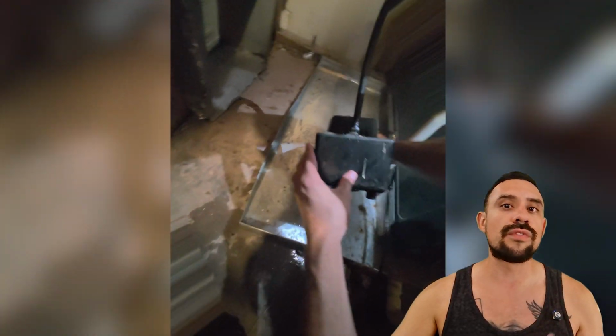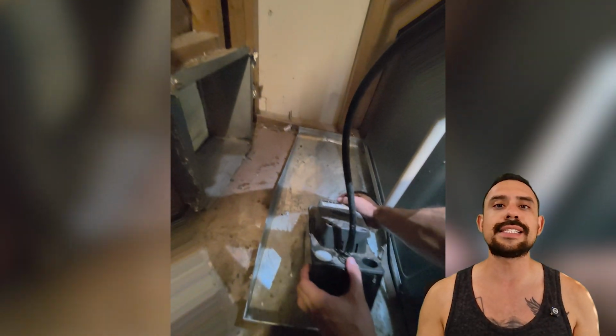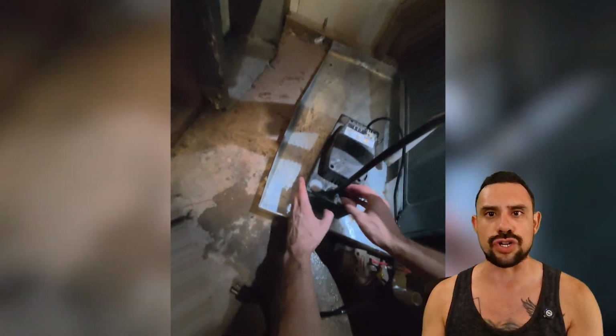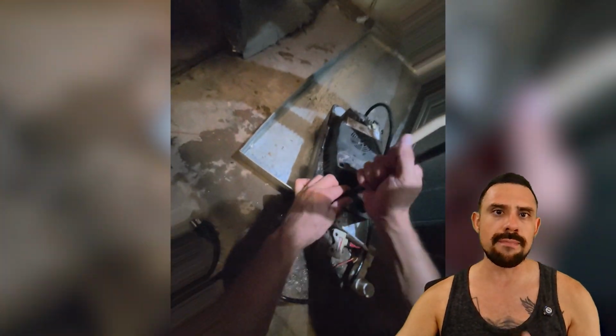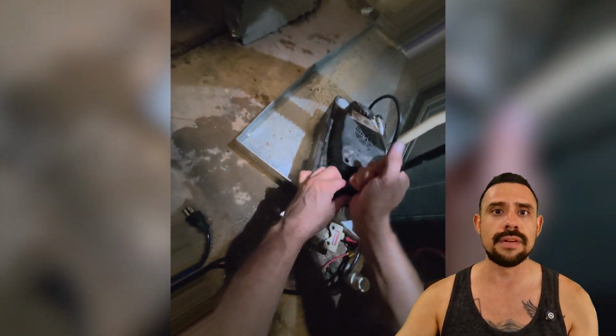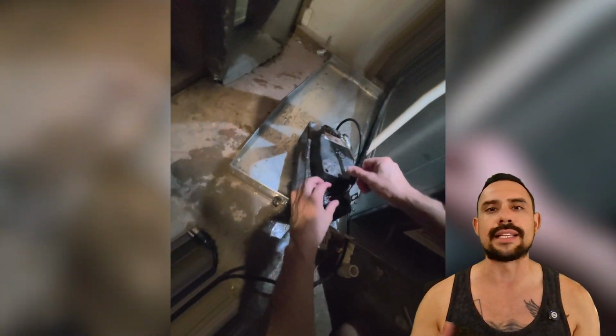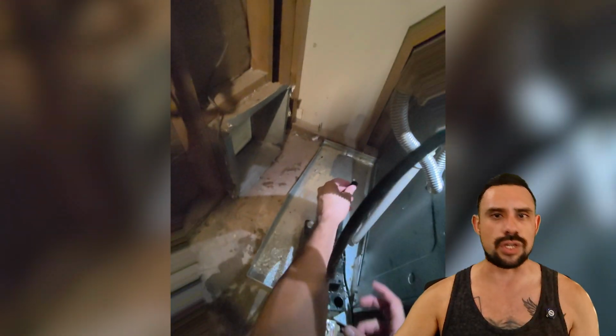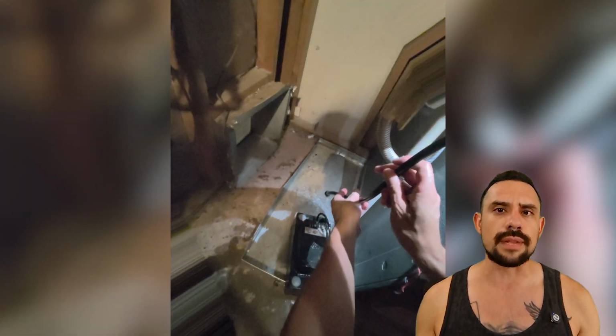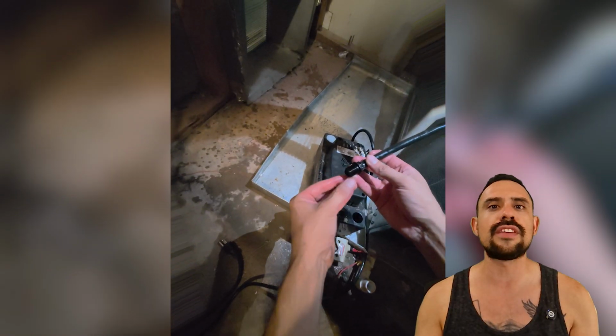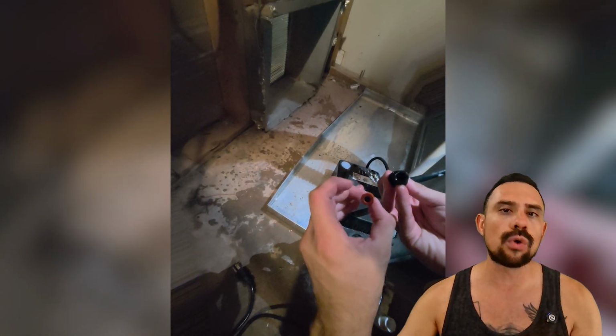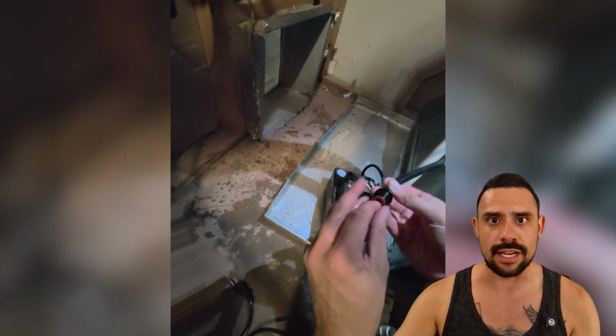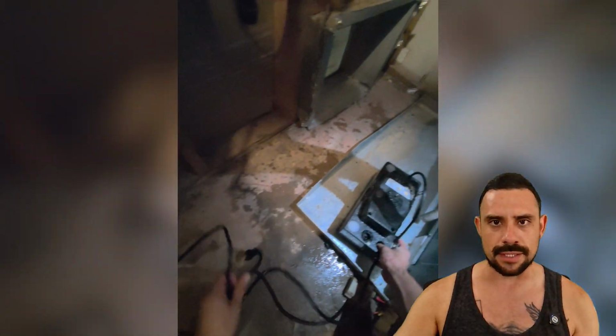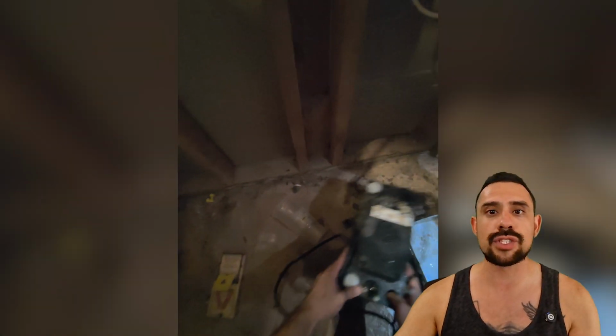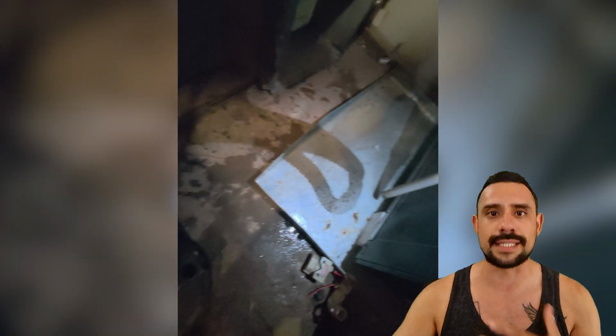To fully remove the old unit, we also need to disconnect the main discharge hose. To remove this hose, simply rotate the locking mechanism counterclockwise until it comes loose, just like you see me doing here. It is incredibly important to note that these hoses feature an internal orange check valve piece that you see here. Do not lose this piece. Keep it secure inside the hose line so both remain intact and accessible.